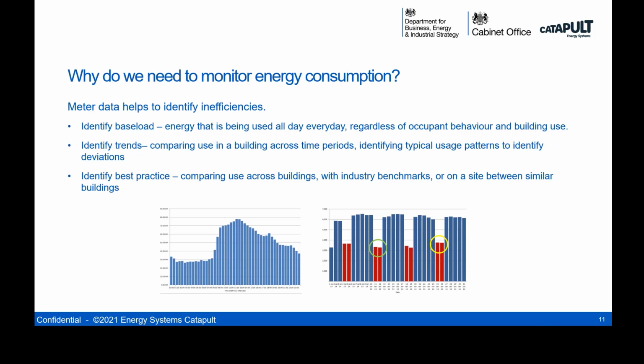The graph on the right shows energy use per day—a total summation of the day's energy consumption. The columns coloured red are the weekends, again when the building is closed. The base load here is approximately 3.5 kilowatt hours per weekend day, just over half of the energy consumption used during the week when the buildings are occupied.